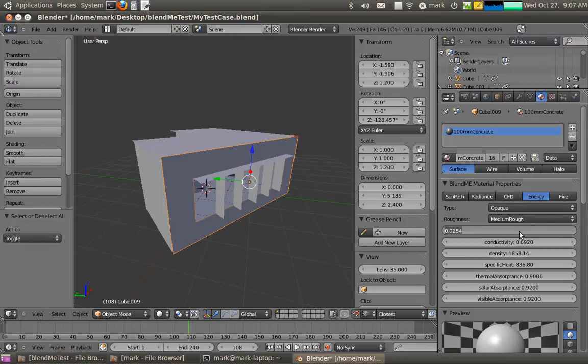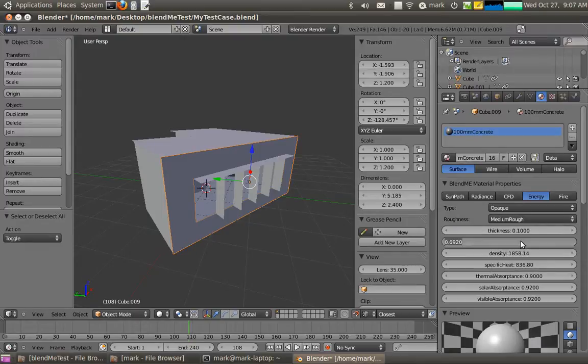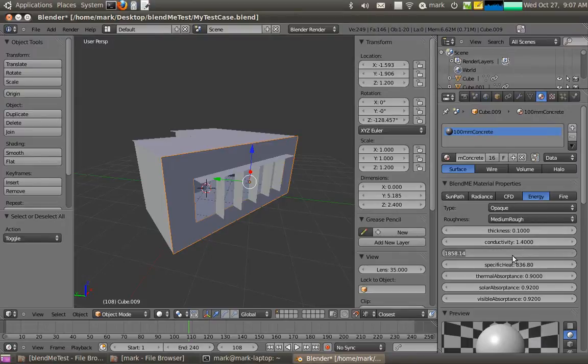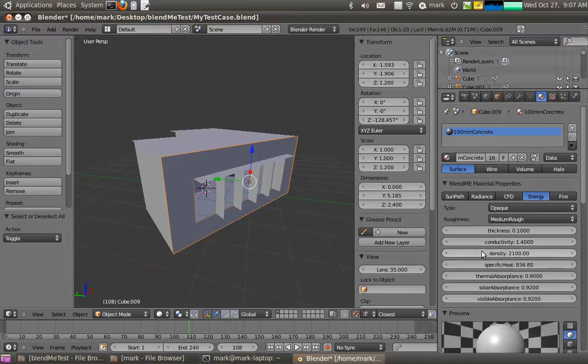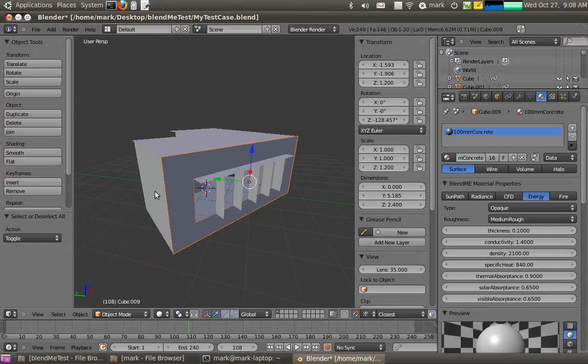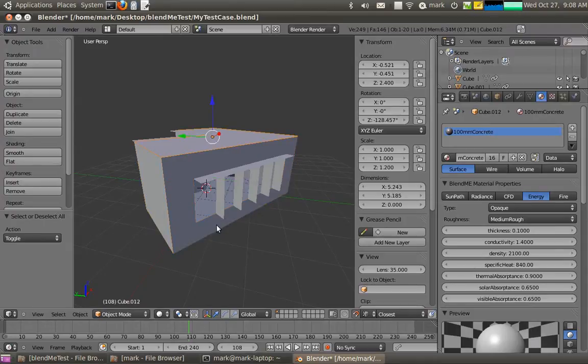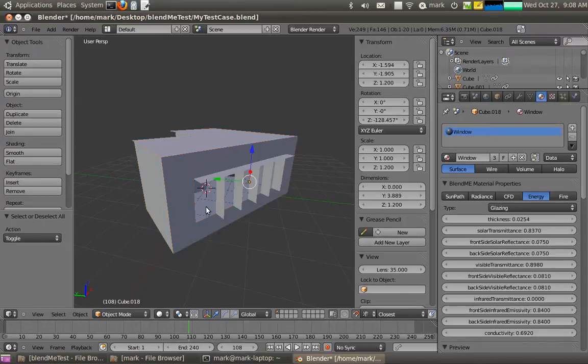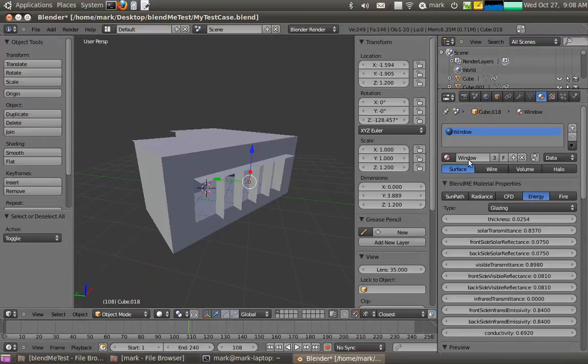There we go. I'll just set this properties for it. Concrete has a conductivity of about 1.4, 2100, 840, that's about right. And we'll make it 0.65 for the absorptance, pretty light colored one. Now you can see that's changed the material across all of it, all the objects that are assigned that.